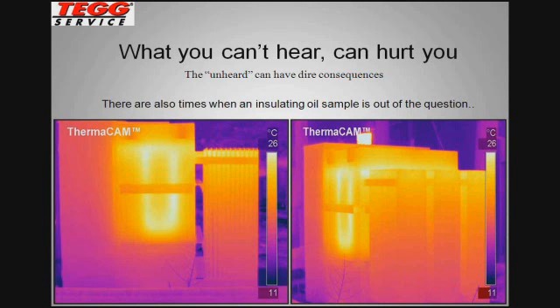So the efficiency was out the window. The life expectancy of the unit was dramatically reduced. And this is a perfect example of what you don't want to see on a liquid-filled transformer. Now, was there ultrasonic emissions on this one? Not yet. But without the insulating oil, as loads are added, it will put stresses on the insulating material, ultimately break it down, and odds are you will have ultrasonic emissions down the road.